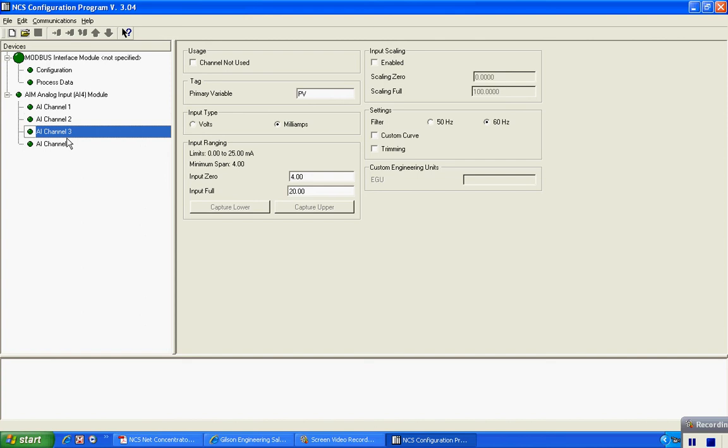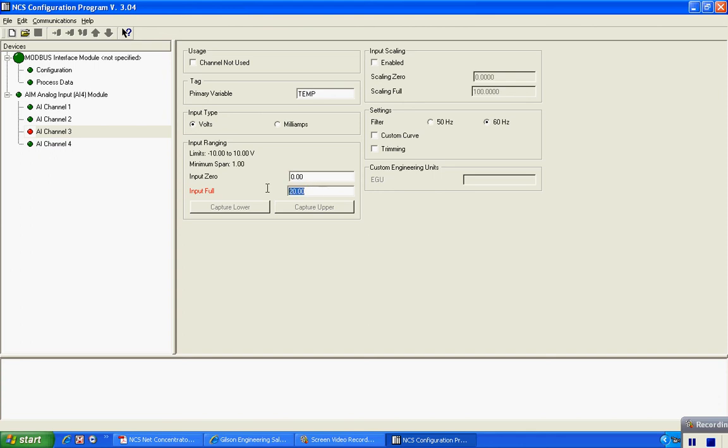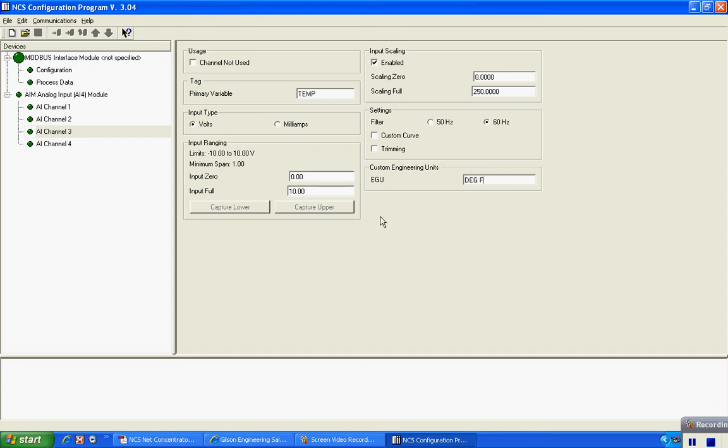So in channel 3, I have a 0 to 10 volt signal coming in. That's in terms of temperature. I can then change my scaling here to 0 to 10 for my volt input, and then I'm going to scale it 0 to 250 degrees F, and I can do that for the fourth channel also.